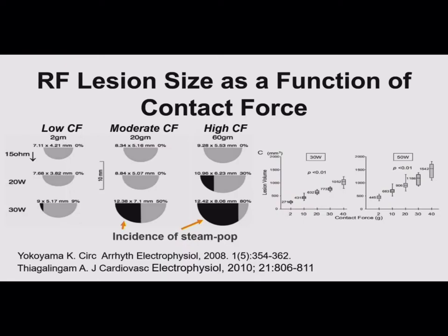Shown nicely by Hiroshi Nakagawa: at any given power, if you increase the contact force between the electrode and the tissue and you're embedding the electrode into the tissue, you'll get a larger lesion. At 2 grams versus 20 grams versus 50 to 60 grams, because you're embedding that electrode in the tissue, you're going to get a larger lesion at different powers. It's when you have both high power and high contact force that you're at the highest risk of creating steam pops.